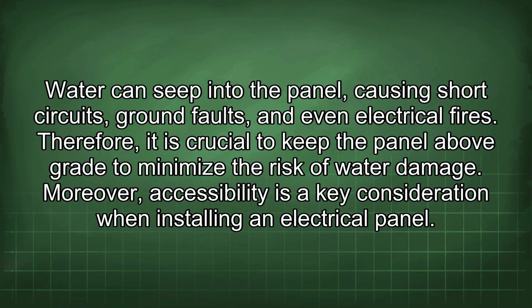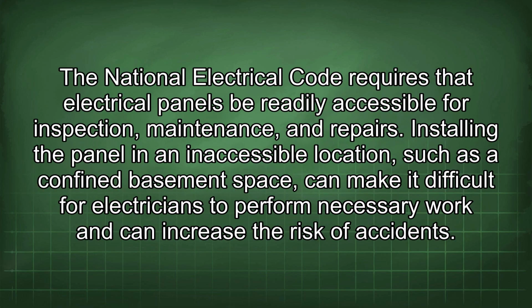Therefore, it is crucial to keep the panel above grade to minimize the risk of water damage. Moreover, accessibility is a key consideration when installing an electrical panel. The National Electrical Code requires that panels be readily accessible for inspection, maintenance, and repairs.